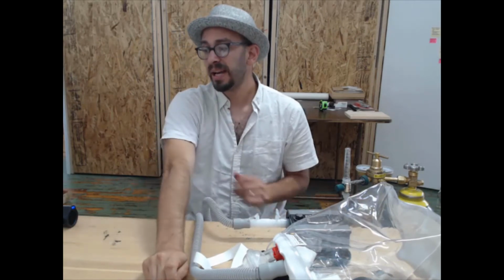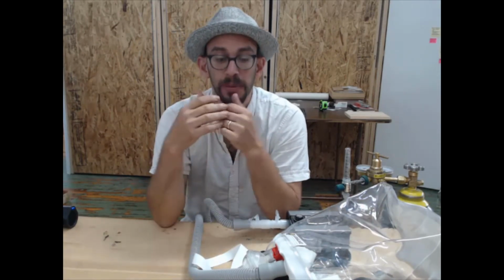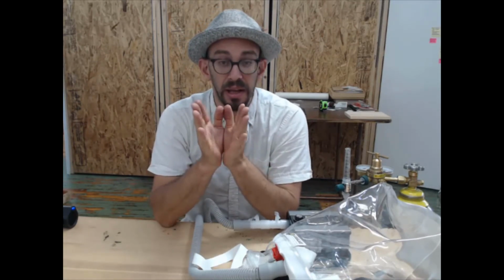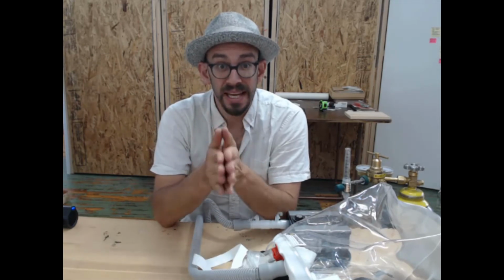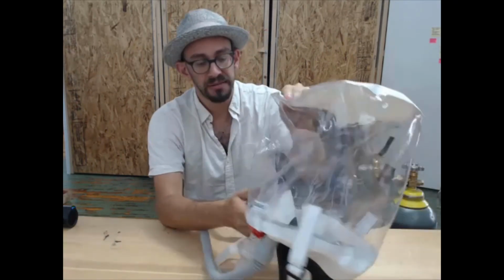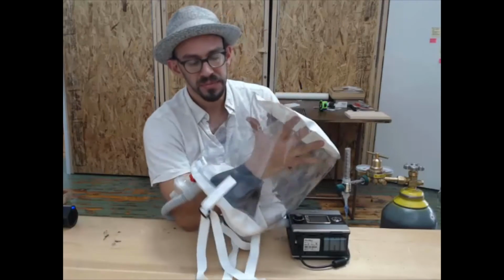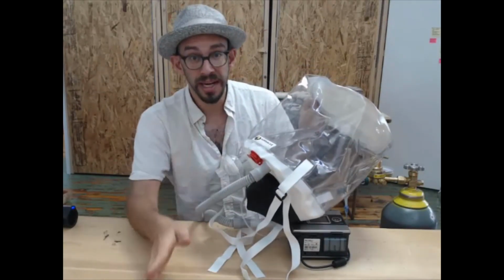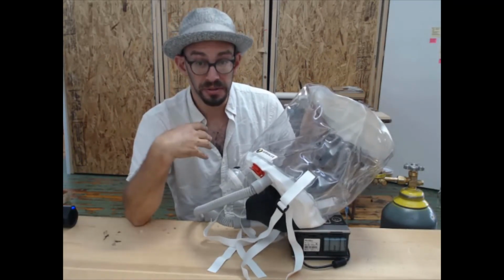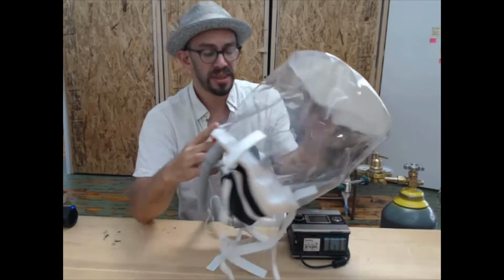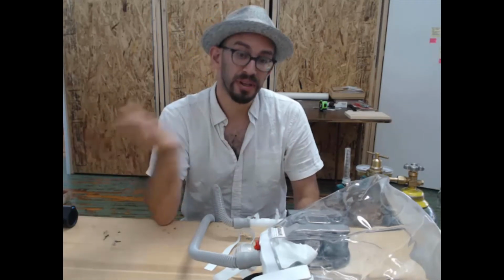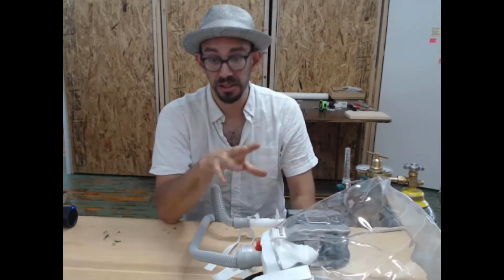So now let's go ahead and think about delivering a pressure to our patient. First of all, as far as patient safety, the key thing to keep in mind is ensuring adequate flow through the system. There's a lot of dead space in this treatment hood, and what you want to avoid more than anything is the patient rebreathing expired air and rebreathing CO2. So to avoid that, we flow a minimum of 50 liters a minute of air through the circuit to flush CO2 out of the dead space in the circuit.